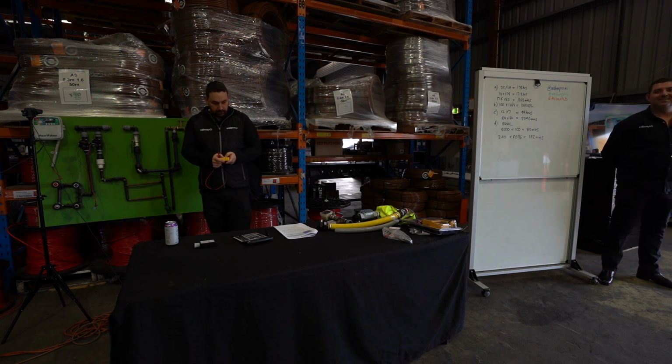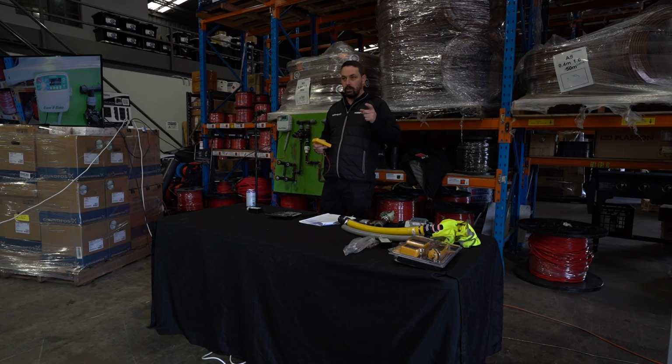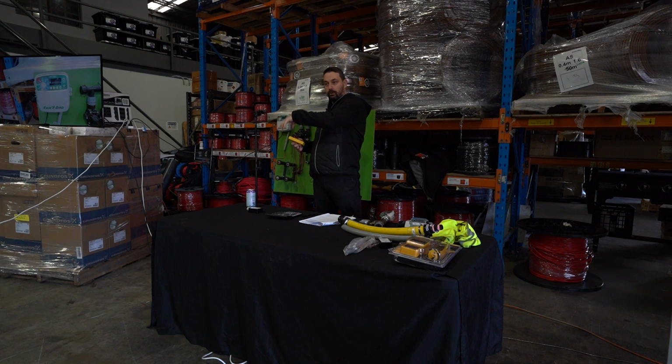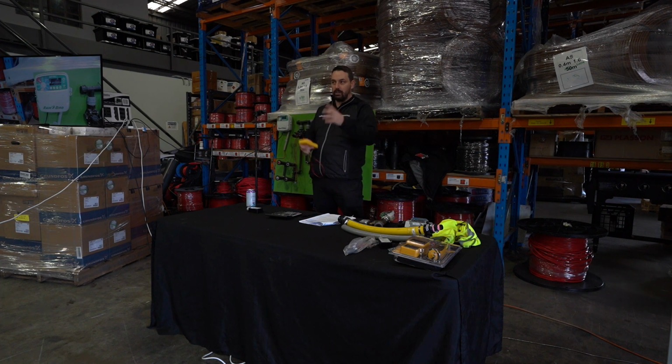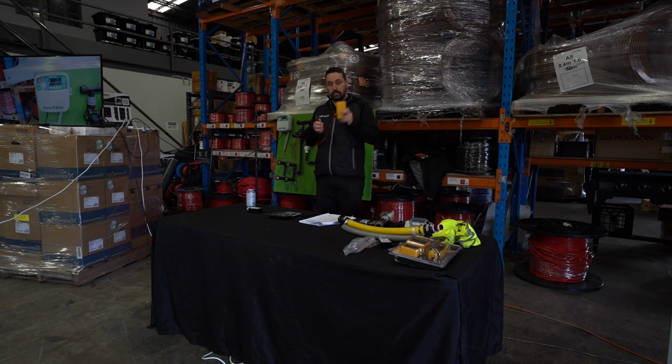One thing that happens a lot is we don't know whether we've got faulty cabling or a dead coil on the solenoid valve. We do tests, people go out and take coils out, change it over, redo wire joins, all that sort of stuff. A lot of the times we don't need to do that. We can just literally use a cheap multimeter to figure out what's happening. This works on an AC coil, where we look for ohms of resistance on a multimeter.